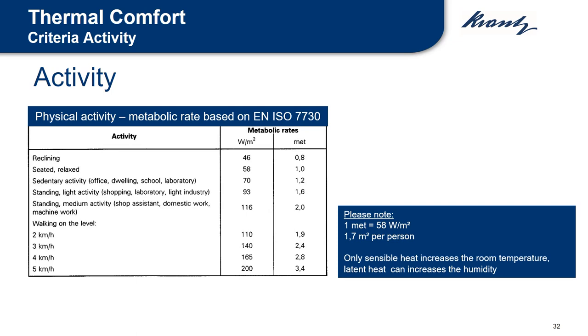The presented table provides us the metabolic rates in Met and watts per square meter according to the daily activity. 1 Met is equivalent to 58 watts per square meter. Those rates are important to calculate the total heat load in a specific space, remembering that sensible heat increases the room temperature, but latent heat can also increase the humidity.